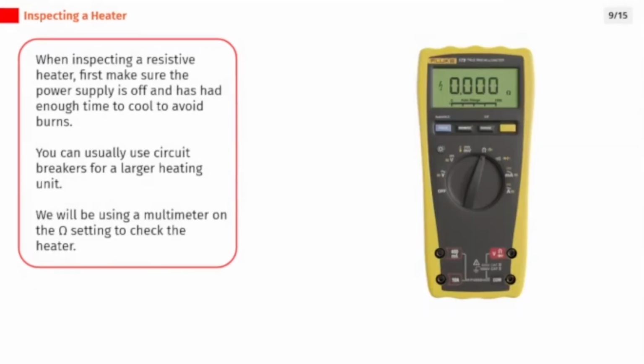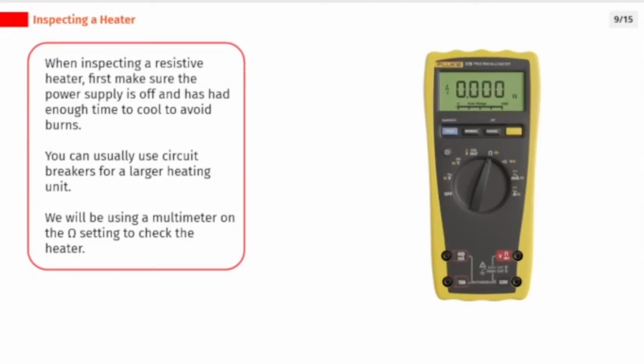When inspecting a resistive heater, first make sure the power supply is off and has had enough time to cool to avoid burns. You can usually use circuit breakers for a larger heating unit. We will be using a multimeter on the ohm setting to check the heater.